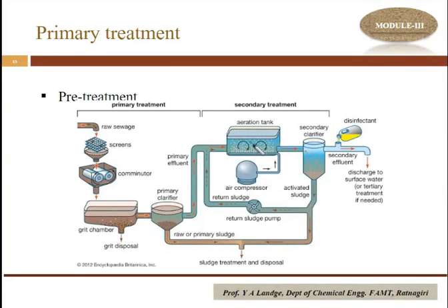So what we do is withdraw some of the microorganisms, not all of them, from this tank and place them into the secondary clarifier, where the microorganism mass settles down. The cells settle here and are used as sludge, and then the water is given to the next step, called disinfection. Here we can use some chemicals or UV light so that it can be used for drinking, or we can send it to the tertiary treatment.